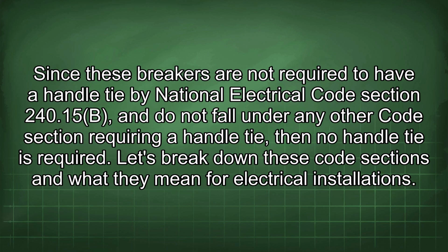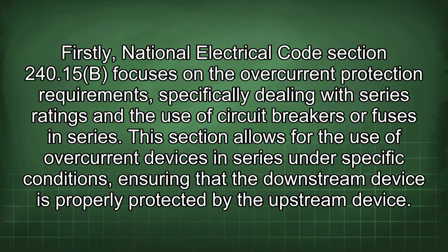Since these breakers are not required to have a handle tie by National Electrical Code Section 240.15(B) and do not fall under any other code section requiring a handle tie, then no handle tie is required. Let's break down these code sections and what they mean for electrical installations. Firstly, National Electrical Code Section 240.15(B) focuses on the overcurrent protection requirements, specifically dealing with series ratings and the use of circuit breakers or fuses in series.